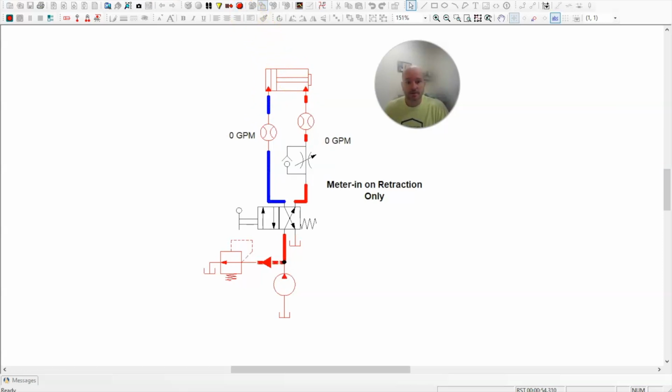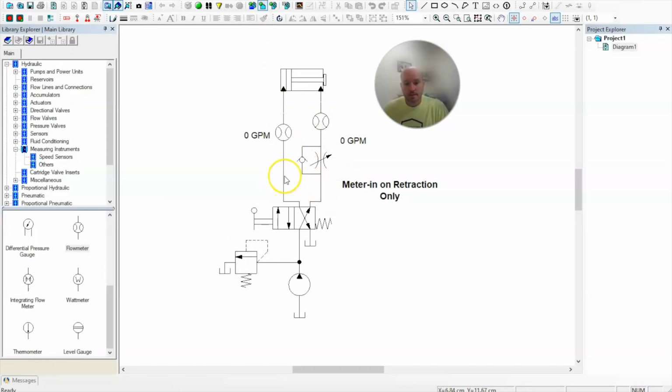So let's talk about this for a little bit. In this circuit, there are a couple of things that you need to be aware of. One, we can right away know this is a meter in circuit because the arrow of the check valve is pointing towards the cylinder. That's just a little visual trick you can use to know if it's meter in or meter out. So this one's being metered in because the arrow is pointing towards the cylinder.